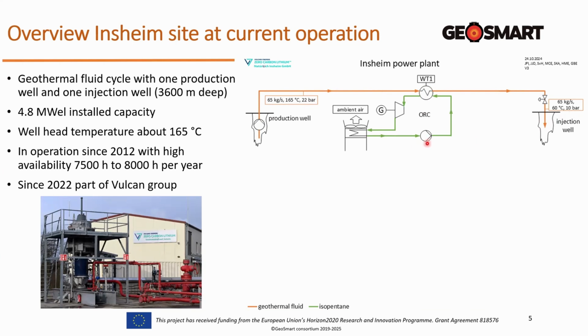On the other side of the cycle, heat is transferred to a working fluid, in our case isopentane. A pump increases the pressure of the liquid isopentane, which is then fed through the vaporizer and preheaters and vaporized by the heat of the geothermal fluid. The high pressure gaseous isopentane flows through a turbine, driving a generator to produce electricity. The isopentane leaves the turbine in gaseous form and then needs to be cooled down and condensed back to liquid so the cycle can restart.